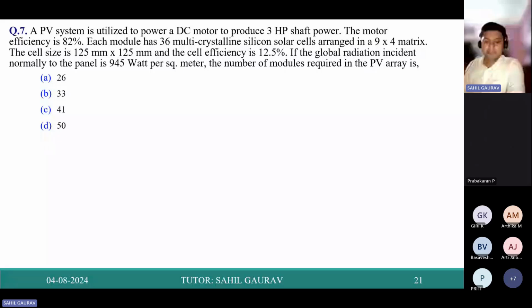Input power required for the motor. If input power to the motor will be this 3 HP shaft power, but the motor efficiency is 82% only, so we have to provide more power than this 3 HP.